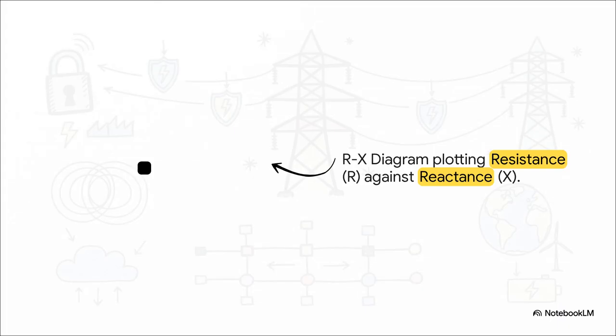Okay, so we have the raw algebra of voltage divided by current, but just staring at an endless stream of numbers really isn't the best way to catch an intruder. Engineers needed to translate that dense algebra into visual geometry. And that gives us the RX diagram. It's honestly a masterpiece of electrical engineering. We plot the line impedance, which is represented as Z equals R plus JX, right on a graph. Your horizontal axis is resistance, or R, and the vertical axis is reactance, or X. Mapping it out like this creates a beautifully clear, defined visual boundary. You can physically see the safe load area versus the dangerous fault zones. If the relay's real-time calculation drops into a specific geometric shape on this graph, boom, it trips the breaker.